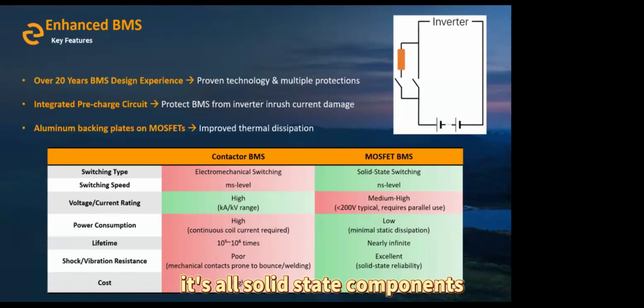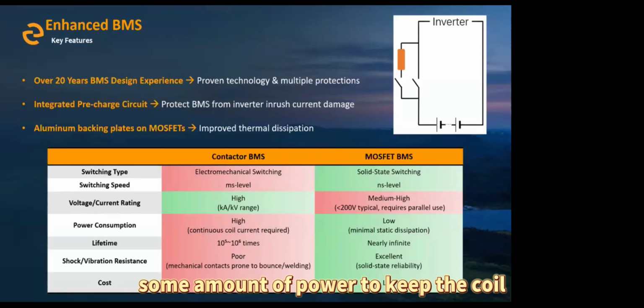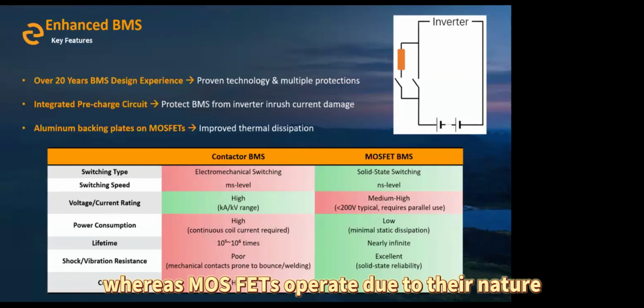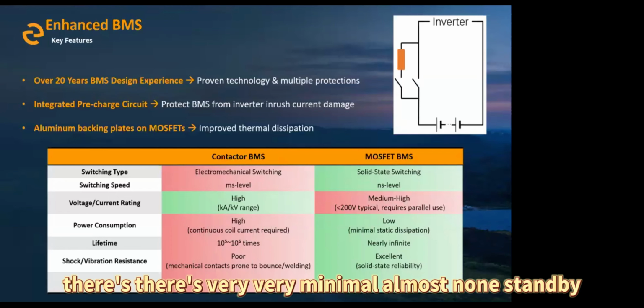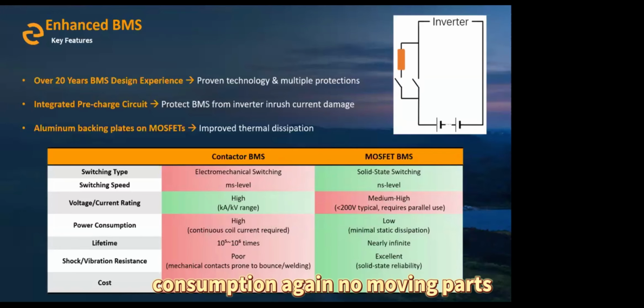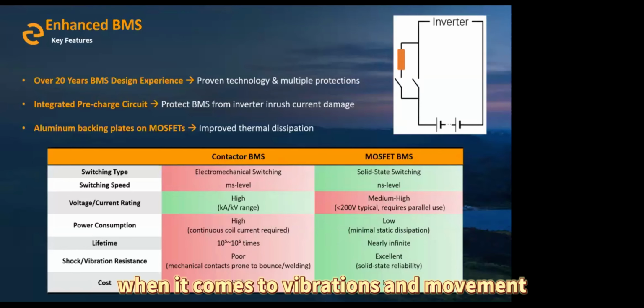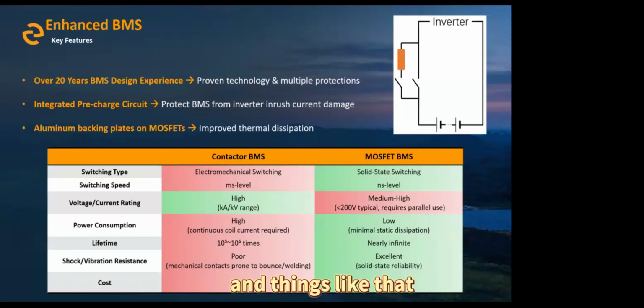It's all solid state components, so it's a lot more efficient as well. A contactor BMS needs some amount of power to keep the coil either open or closed, whereas MOSFETs operate with very, very minimal, almost no standby consumption. Again, no moving parts means it's got a higher lifespan and a much higher reliability when it comes to vibrations and movement.